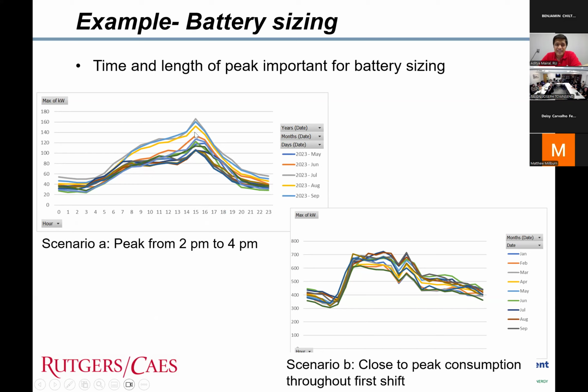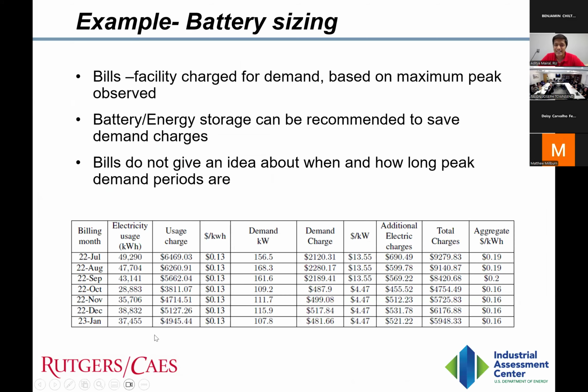Scenario 1 here shows that this peak only lasts for 2 hours, whereas here the peak lasts for about 8 hours. Meaning that if I size a battery for, say, 160 kilowatts - I need that 160 kilo, again it won't be exactly 160, I'll get to that point in a minute - but I want that 160 kilowatts to last for 2 hours to get rid of this peak, whereas here I want it to last for 8 hours. So the energy required in scenario B is going to be much higher, meaning we need a bigger battery. And then the cost will increase, which I won't be able to know if I just look at this data. So my implementation cost will be all over, and it won't make for a good recommendation for the facility.